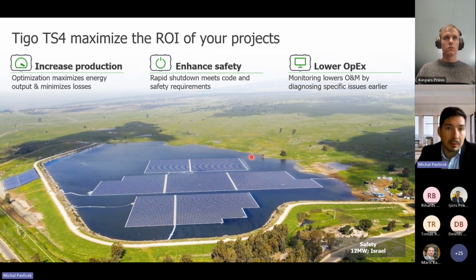These floating power plants have their specifics, because whenever you would like to enter the pontoon with the modules, which is on the water, you are always at risk of getting injured by the electrical current. Why? Because of the high humidity, you are on the water, so it's always dangerous to go there when the power plant is in operation. Thanks to the feature, which is a rapid shutdown control, you can switch off the power plant. In fact, you can switch off just segments which you need to operate and do some service. And thanks to this function, you reduce the voltage to 0.6 volt at the individual modules. That allows you to enter the power plant safely, and to have in the strings also the voltage below 24 volts, so you can even touch wires with your hands. So safety it is.